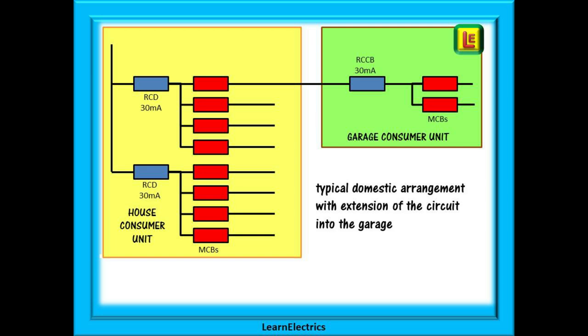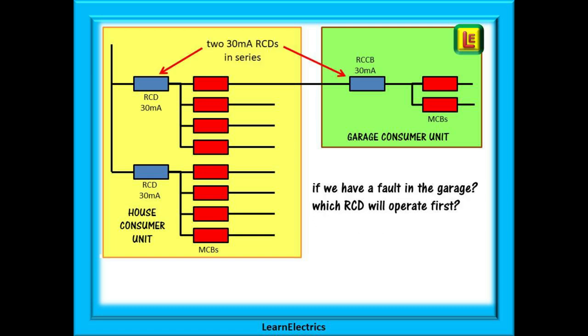If we look at a typical domestic installation a circuit has been taken from the consumer unit to the garage. At the garage a small two circuit consumer unit is installed. This contains a 30 milliamp RCCB and two MCBs. We now have two 30 milliamp RCD devices in series with each other one in the house and one in the garage.